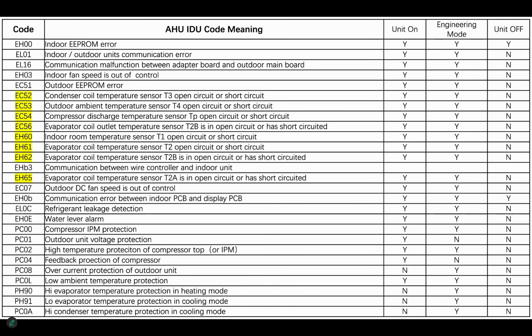Here's what you'll see though. It will still show the sensor error. So if you see one of these sensor errors, don't always assume that the problem is with that particular sensor. The system periodically polls all the sensors. If you have a problem with the 5-volt DC bus and the bus goes down when it polls a sensor, it may not show that sensor as the problem. It may show another sensor as the problem, because when the bus comes back up, it sees that particular sensor.